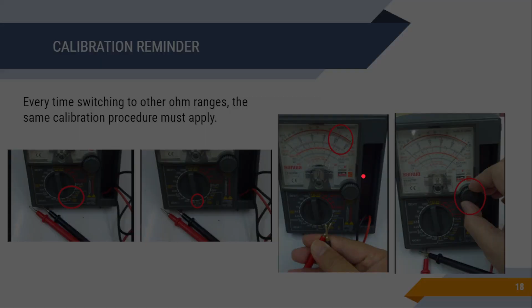A reminder on calibrating: every time you switch to another ohm range, the same calibration procedure must apply. For example, we're going to change the range from times 1 to times 100. If we do that, then try to short the probes, the result here would be different. It won't be exactly at 0. That's why we need to apply calibration every time we change ranges.